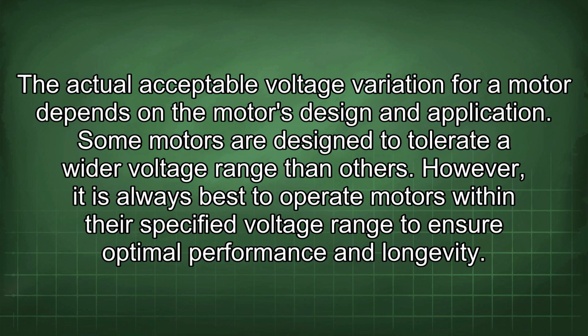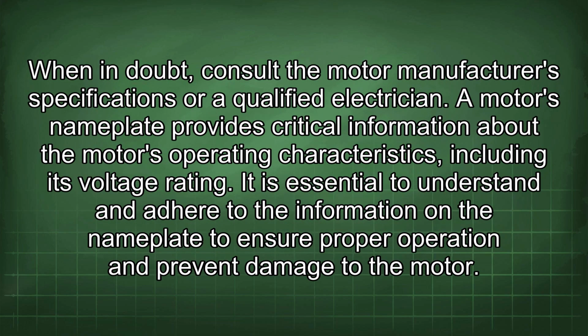The actual acceptable voltage variation for a motor depends on the motor's design and application. Some motors are designed to tolerate a wider voltage range than others. However, it is always best to operate motors within their specified voltage range to ensure optimal performance and longevity. When in doubt, consult the motor manufacturer's specifications or a qualified electrician.